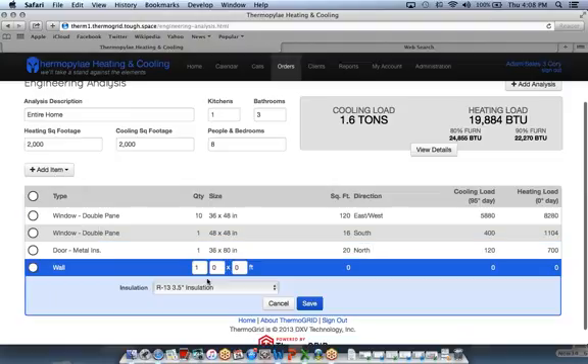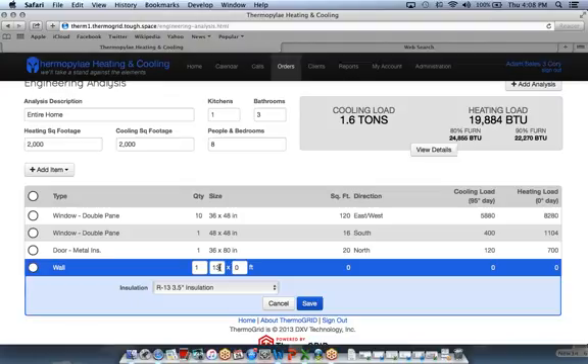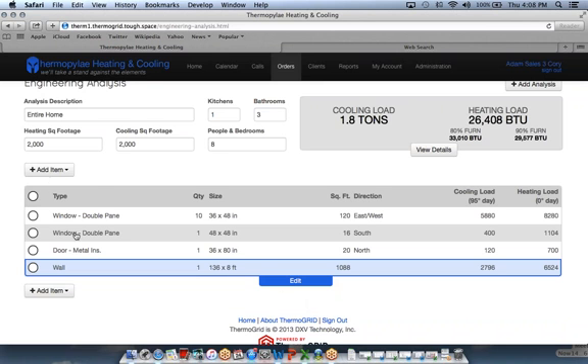When it comes to the wall, the wall is going to be your outside perimeter of the home of anything that's being conditioned. So let's say the perimeter of this home is 136 and the height of ceiling is eight feet. Then we select the type of insulation that's in the walls, the R value.